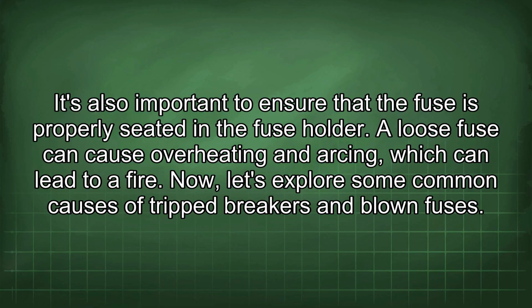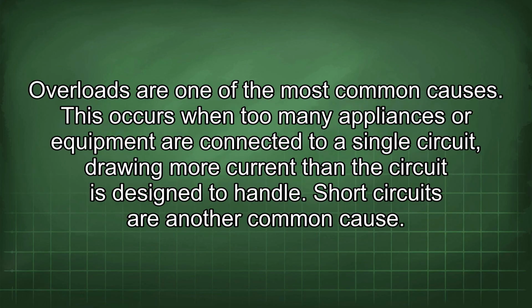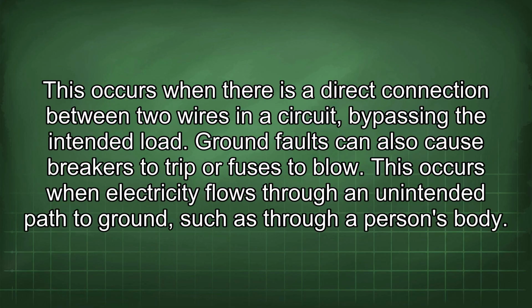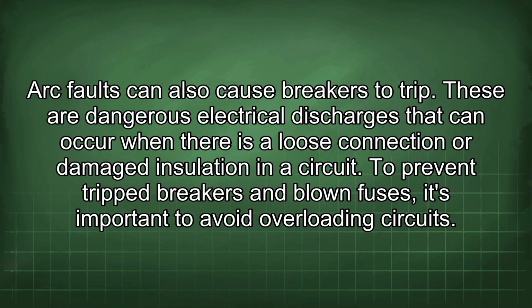Now, let's explore some common causes of tripped breakers and blown fuses. Overloads are one of the most common causes. This occurs when too many appliances or equipment are connected to a single circuit, drawing more current than the circuit is designed to handle. Short circuits are another common cause. This occurs when there is a direct connection between two wires in a circuit, bypassing the intended load. Ground faults can also cause breakers to trip or fuses to blow. This occurs when electricity flows through an unintended path to ground, such as through a person's body. Arc faults can also cause breakers to trip. These are dangerous electrical discharges that can occur when there is a loose connection or damaged insulation in a circuit.